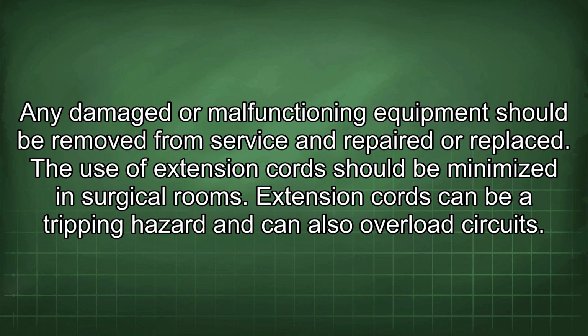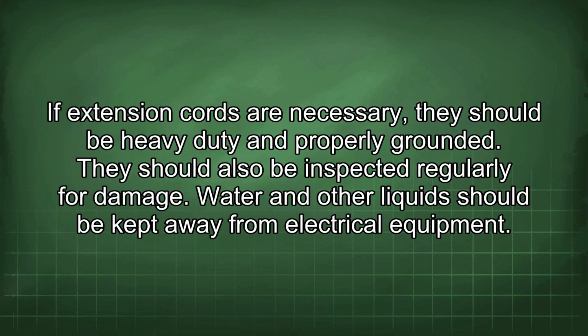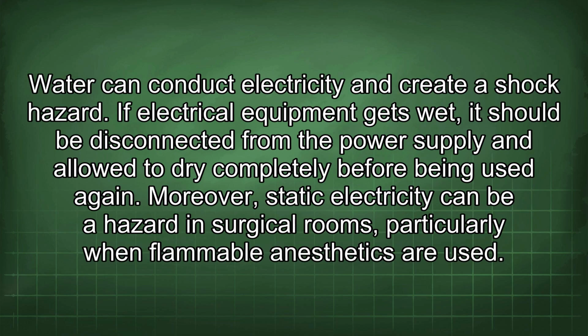The use of extension cords should be minimized in surgical rooms. Extension cords can be a tripping hazard and can also overload circuits. If extension cords are necessary, they should be heavy-duty and properly grounded. They should also be inspected regularly for damage. Water and other liquids should be kept away from electrical equipment. Water can conduct electricity and create a shock hazard. If electrical equipment gets wet, it should be disconnected from the power supply and allowed to dry completely before being used again.